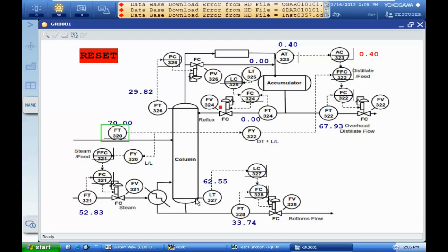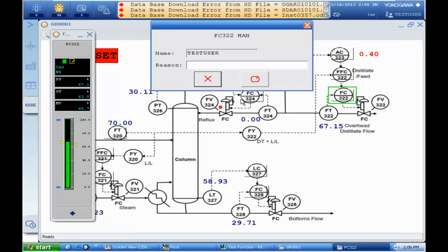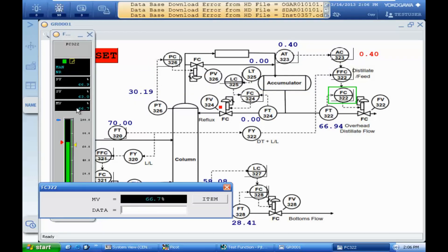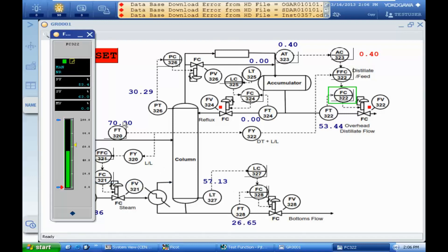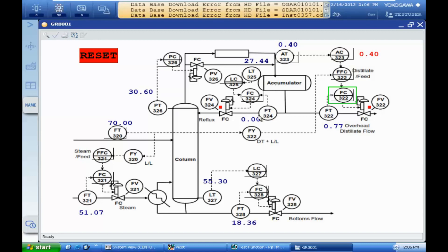The next test will be blocking the product output. I want to change this product output to manual mode and totally close the output. You can see the square indicator here. When the product output is closing, the accumulator level will increase dramatically, and after reaching 50, the reflux flow is increasing in order to maintain the accumulator level.